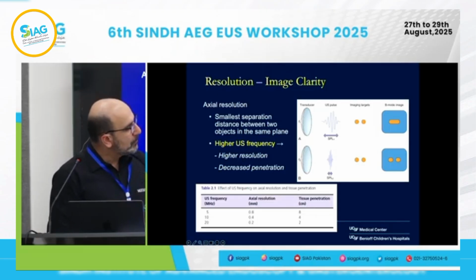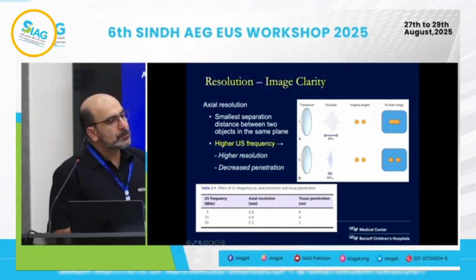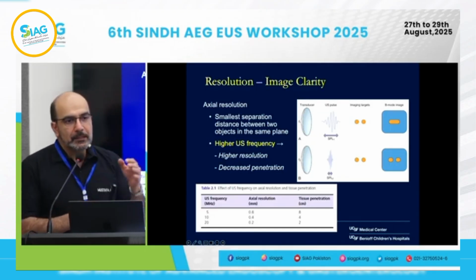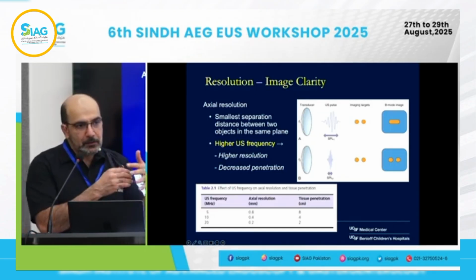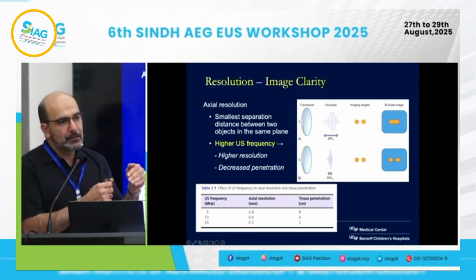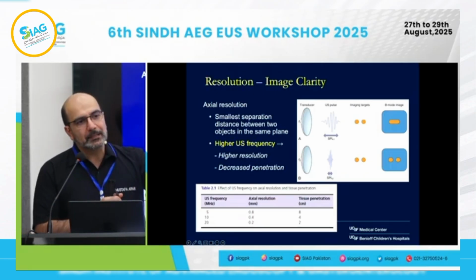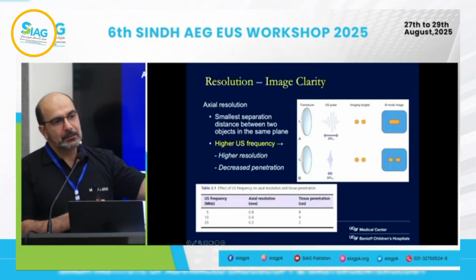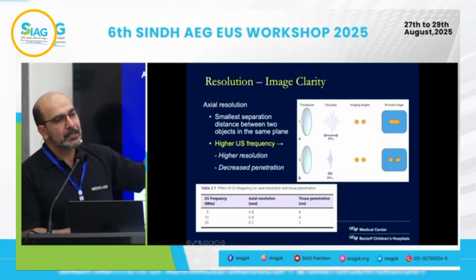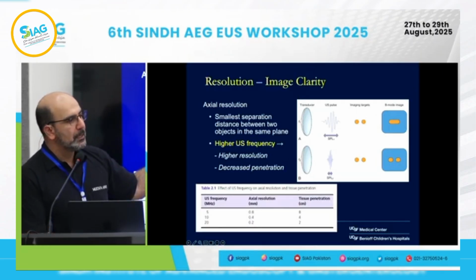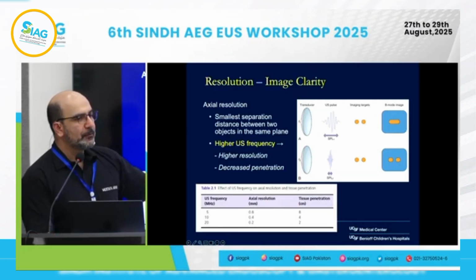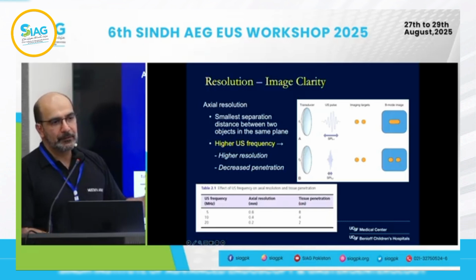So what happens is you lose your depth of penetrance. For submucosal lesions that are small, or something close to the probe, high frequency is good. But if you want depth, say you want to look at something in the liver, you can't do 20 megahertz because you won't get the quality of image that you want in the liver. For that, you have to drop down to 7.5.